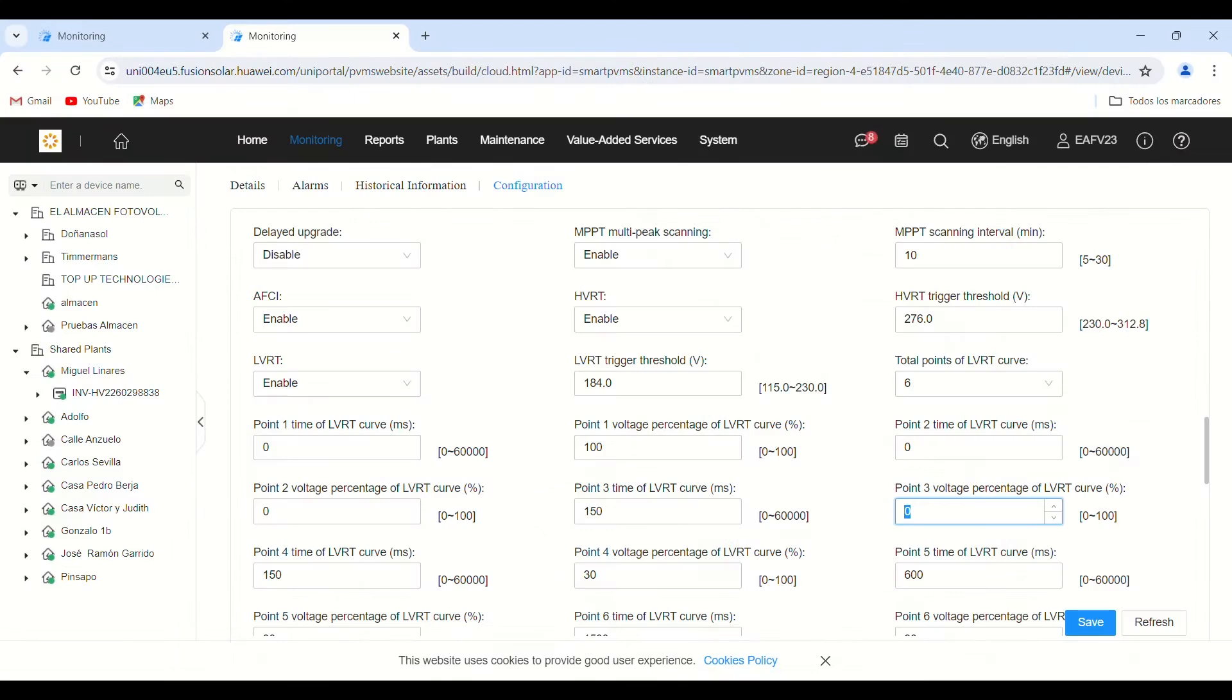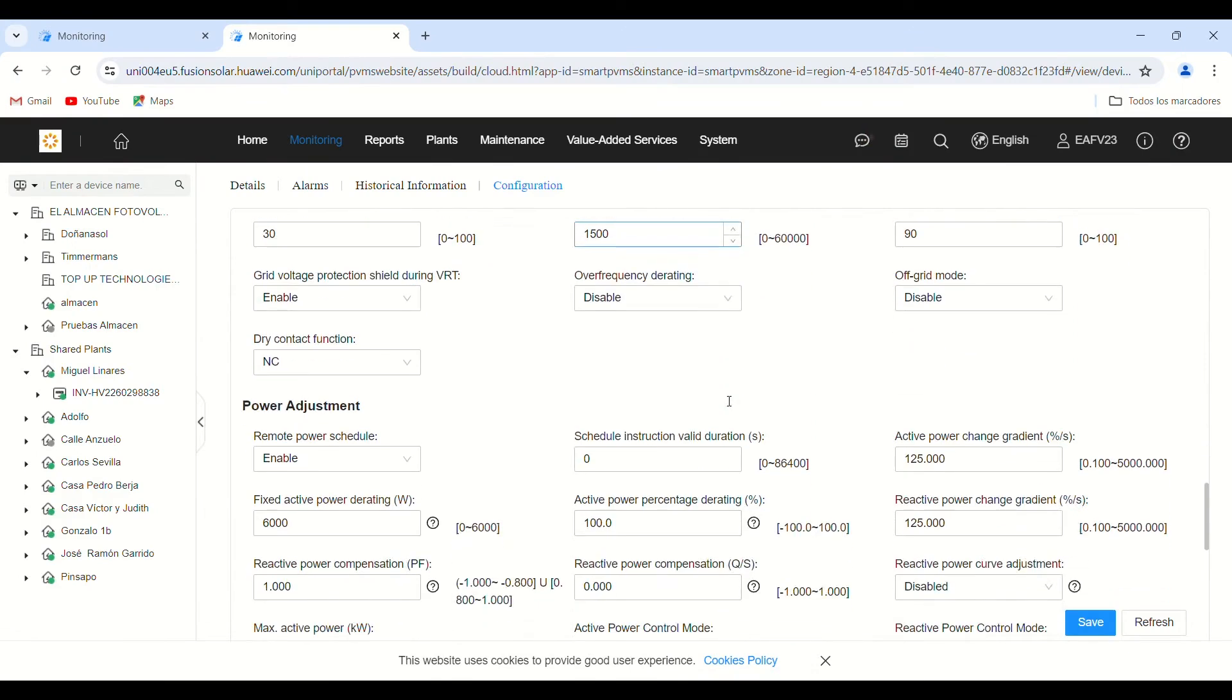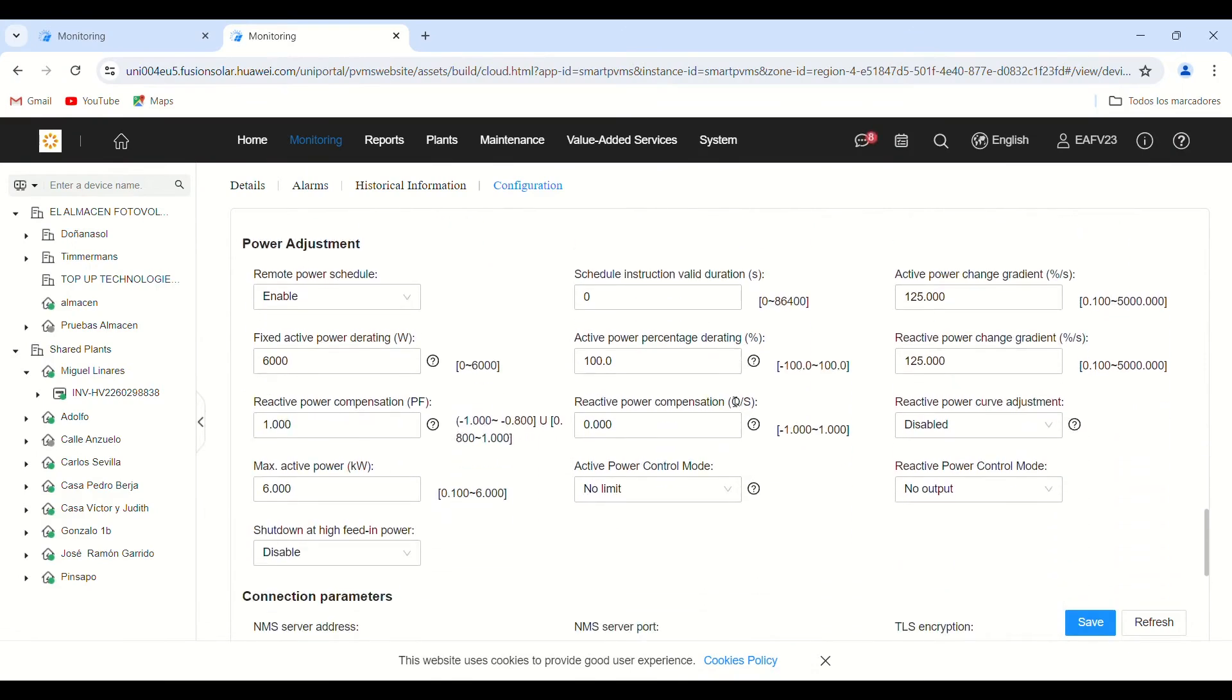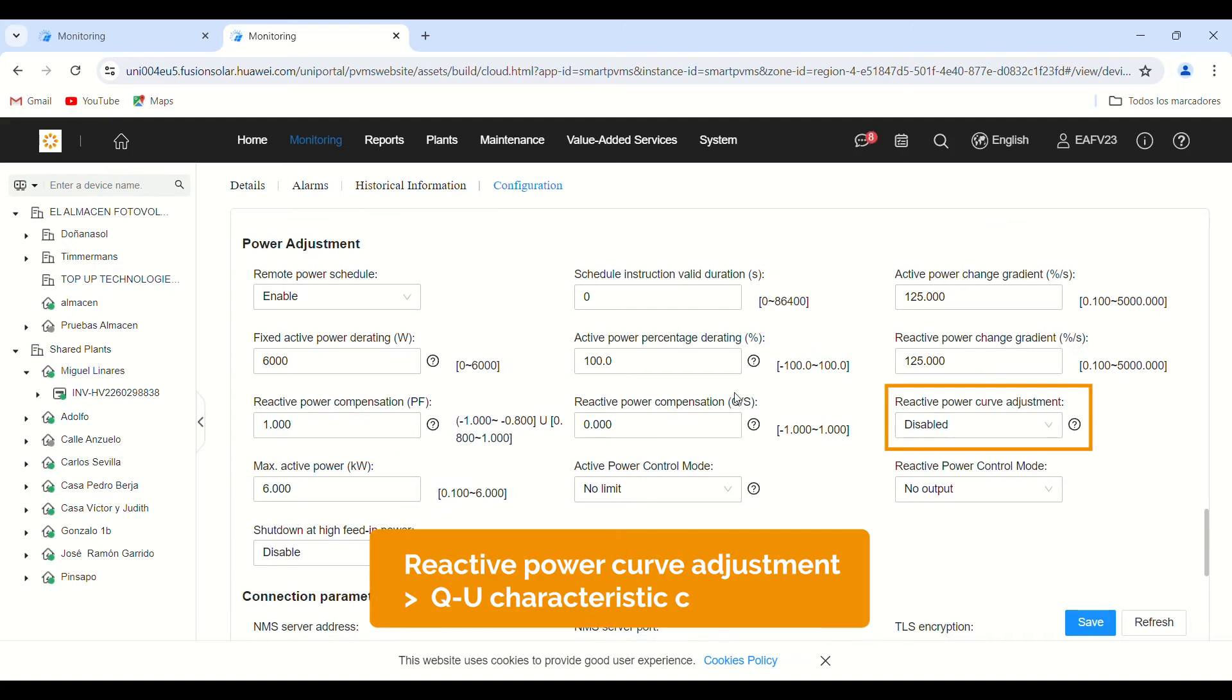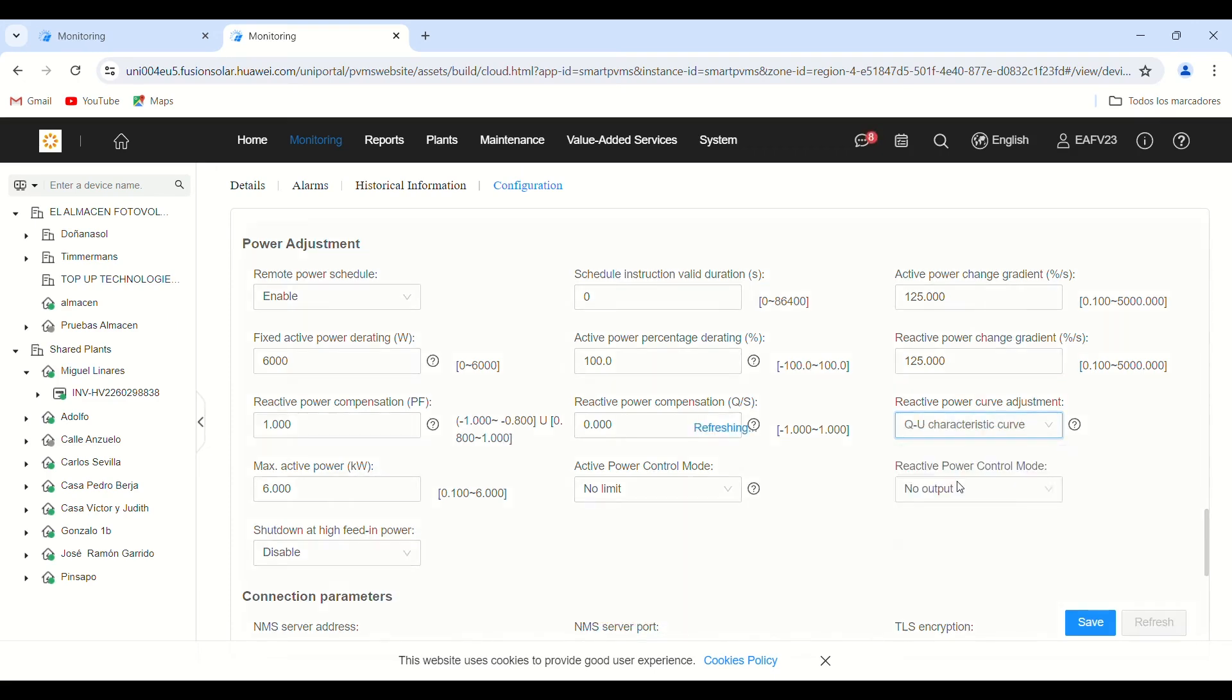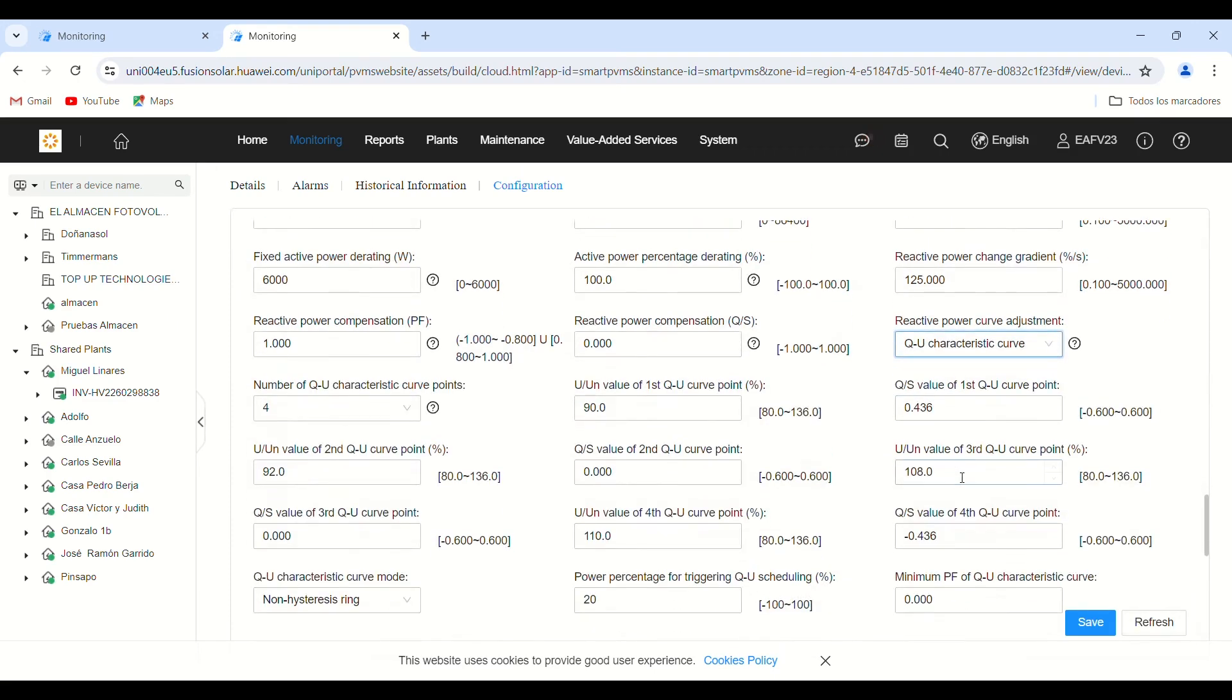The QU characteristic curve control mode dynamically adjusts the ratio between output reactive power and apparent power, based on the ratio between the actual voltage and the nominal grid voltage. By activating this parameter, the inverter will generate reactive power to compensate for the voltage rise.